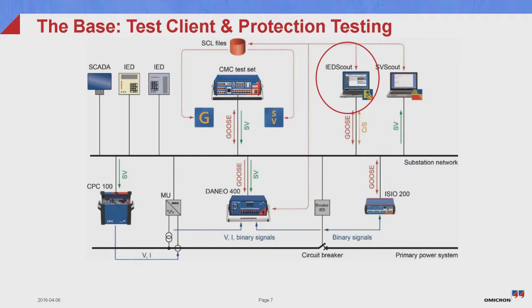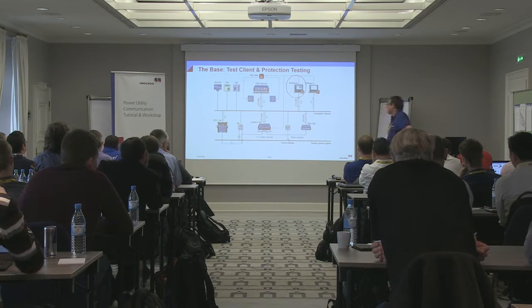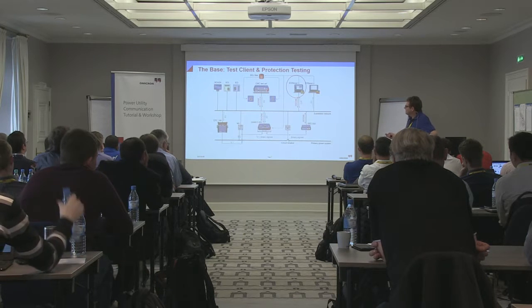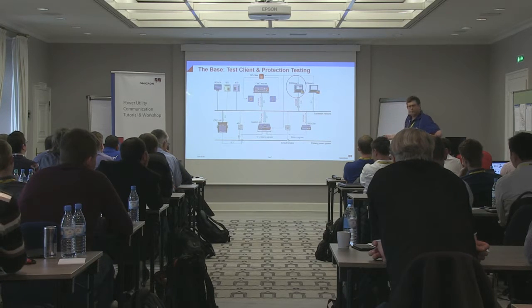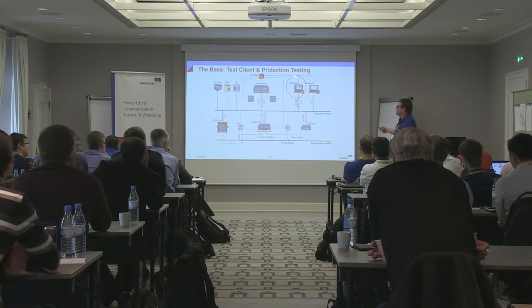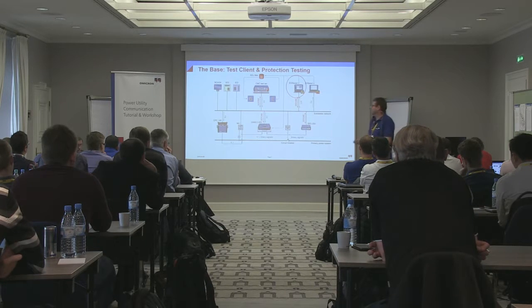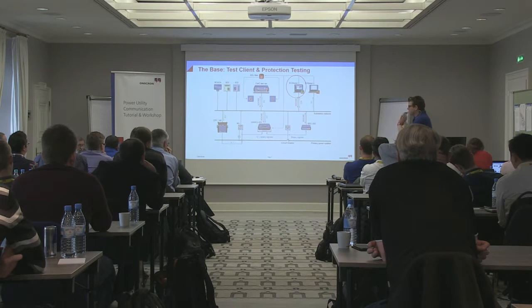So I'm playing the client, because it might be that the real one is not in operation at the moment, and then I can try to test what's going on here in the server, for instance, perform the control and so on. And I also have possibilities with special devices to listen to this point-to-point traffic. If there is a mirror port configured or there is a tap in between, then I can also visualize that. So this is a task done by a test client in a substation, connected to the port, and then communicating point-to-point. This was one task where we started.